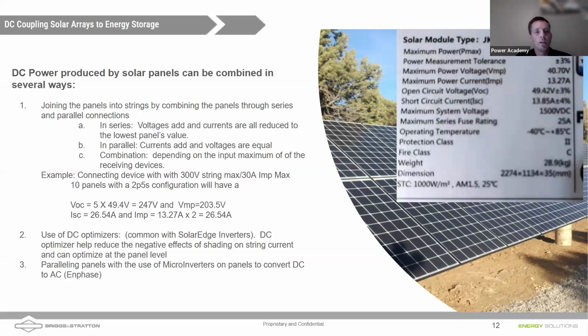Then we'd be looking at a short circuit current of what 2 panels would produce, and an open circuit voltage of that voltage coming from a series of 5. And that would match our charge controller there. Other ways to join panels is through the use of DC optimizers. And so DC optimizers can essentially isolate and optimize panels even on an individual level.